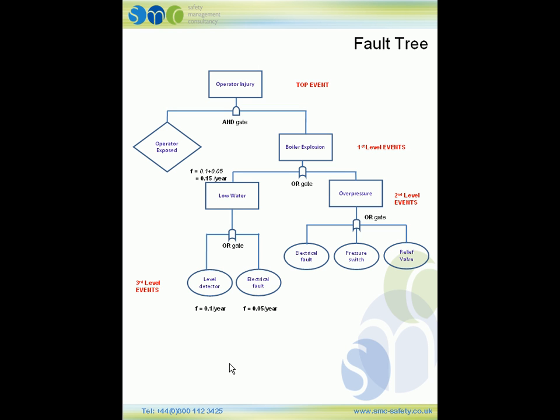For condition B, applying the frequencies to how over pressure could happen: the electrical fault is 0.05 per year, the pressure switch is 0.1 per year, and the relief valve is 0.05 per year. Because this is an OR gate, we add the frequencies: 0.1 plus 0.05 plus 0.05 gives a frequency of 0.2 per year. To get the frequency for the boiler explosion, we add the frequency of the low water plus the frequency of the over pressure: 0.15 plus 0.2 gives a frequency of 0.35 per year.